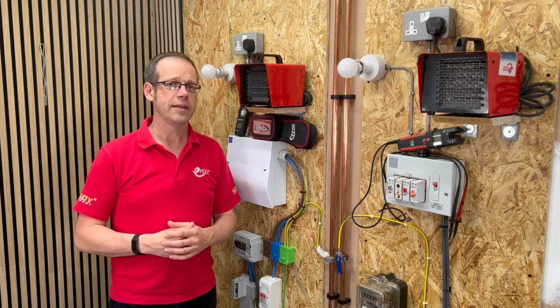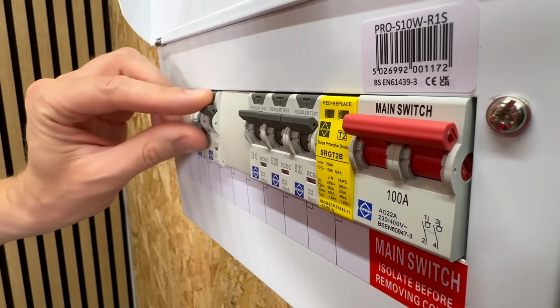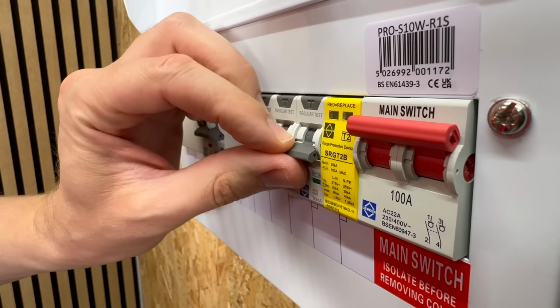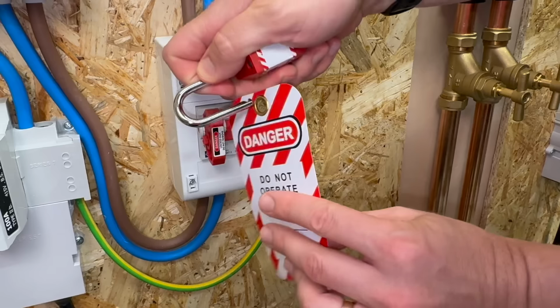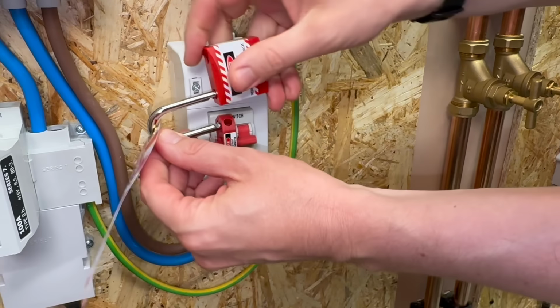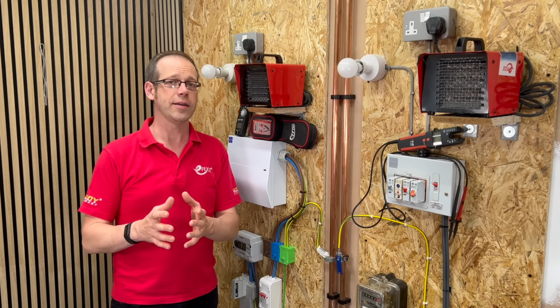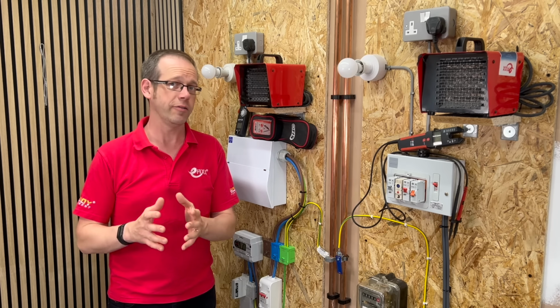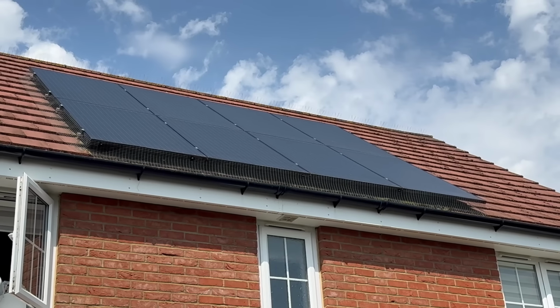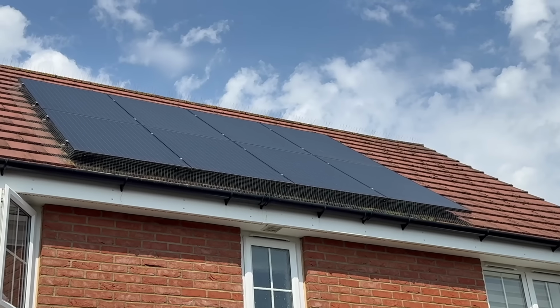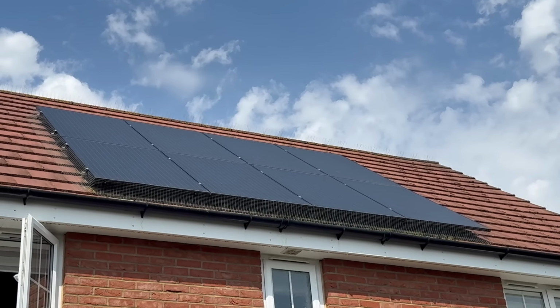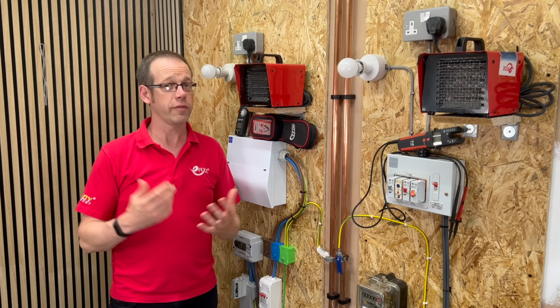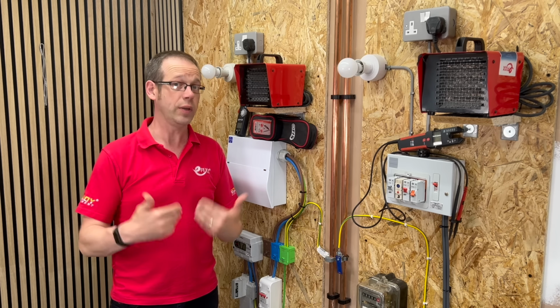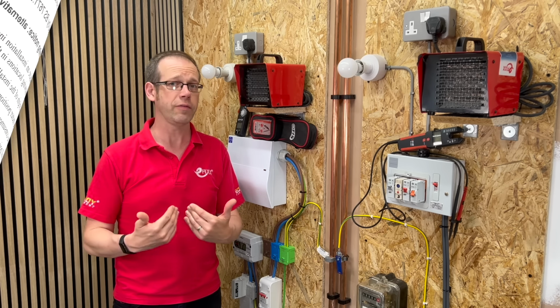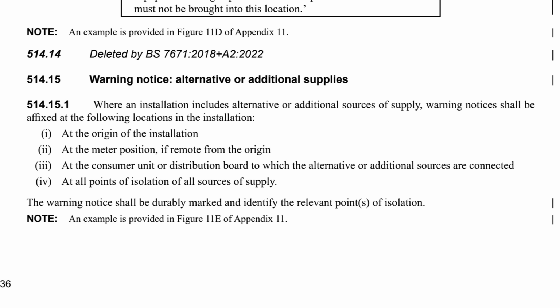So why are we addressing this in a video about safe isolation? Well, because it neatly highlights a potentially dangerous situation whereby you've isolated an electrical installation, again following that tried and tested process, and yet when you open up the board and get to work, it turns out that there's still some very, very live parts being fed by the still happily operating and generating PV system on the roof. So how do we protect ourselves and others from this hazard? Well, safety begins with us, so the first thing to do is to make sure that the installations we work on comply with the regs, in this case specifically 514.15 under the heading Warning Notice, Alternative or Additional Supplies.